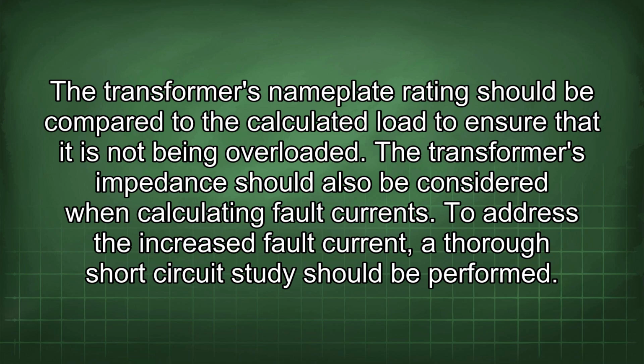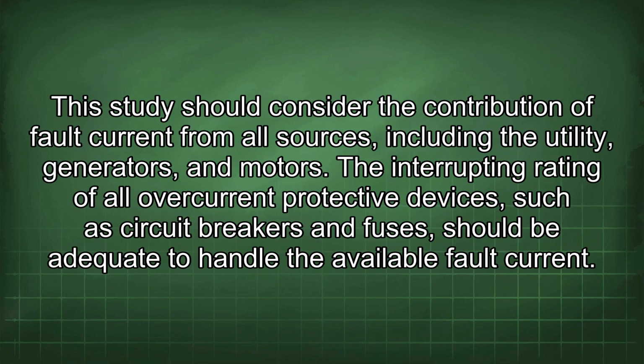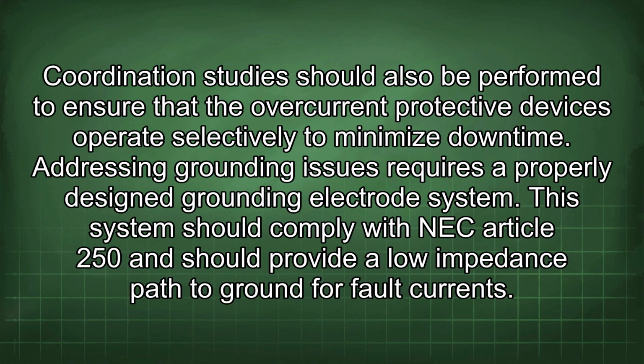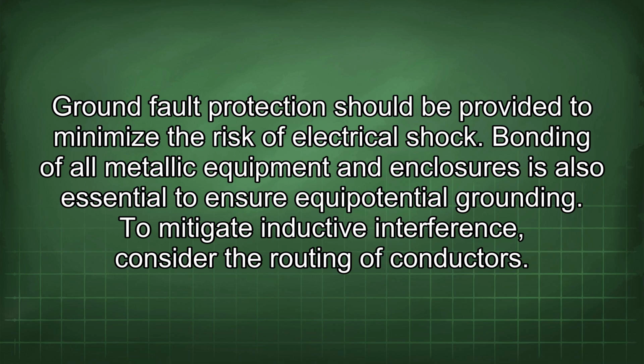To address the increased fault current, a thorough short-circuit study should be performed. This study should consider the contribution of fault current from all sources, including the utility, generators, and motors. The interrupting rating of all overcurrent protective devices, such as circuit breakers and fuses, should be adequate to handle the available fault current. Coordination studies should also be performed to ensure that the overcurrent protective devices operate selectively to minimize downtime. Addressing grounding issues requires a properly designed grounding electrode system. This system should comply with NEC Article 250 and should provide a low impedance path to ground for fault currents. Ground fault protection should be provided to minimize the risk of electrical shock.